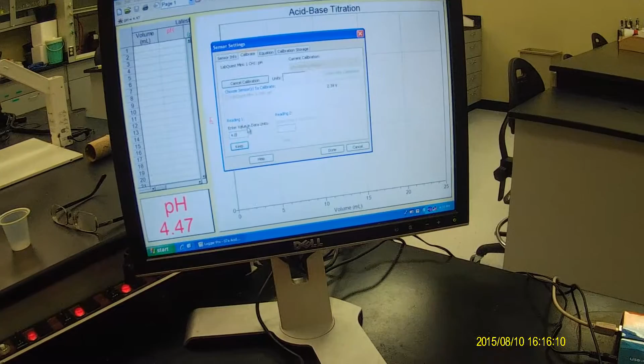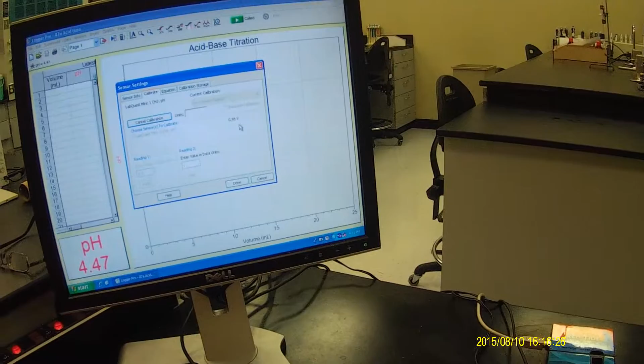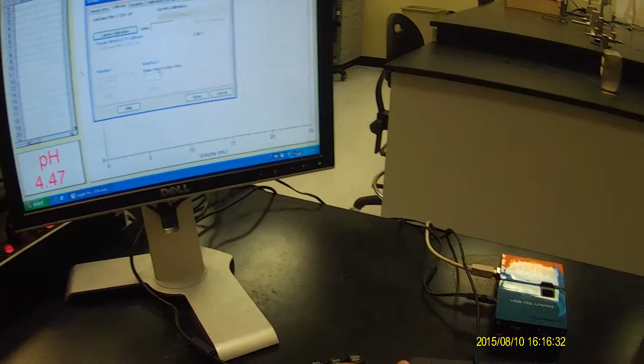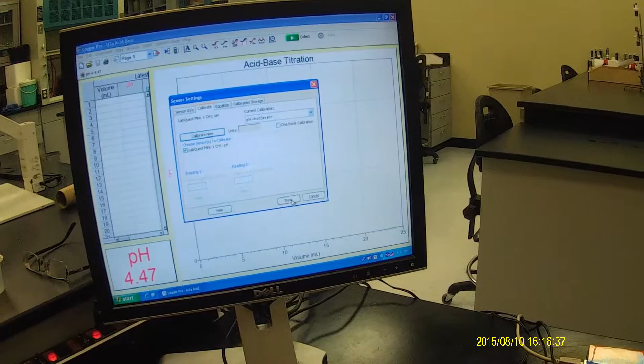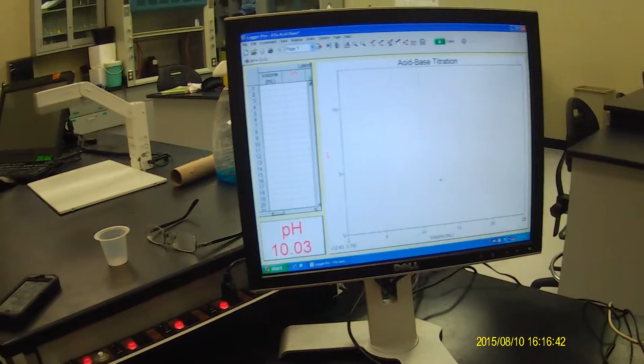And then we'll take our electrode out, rinse it off. We're going to go over here to pH 10. Go into the pH 10 buffer. Notice the voltage will change. Wait for that to stabilize. 0.93. The value of this buffer is 10.0. We'll keep that. And then we'll say done. And we'll notice that the pH should be very near 10.